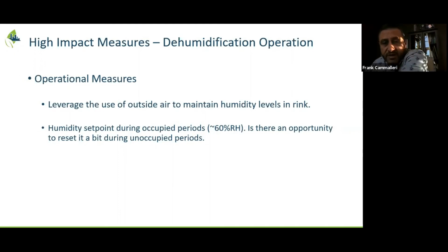Optimization opportunities exist with trying to take advantage of outside air where it makes sense. It's a trade-off with any heating that would be required, but because ice rinks typically don't have high space temperature conditions, the strategy can work quite well. We're finding that on site, humidity set points varied from one rink to the next. We've seen them as low as close to 40%, but we feel there's an opportunity to increase that setting. The higher the setting, the lower the energy required to dehumidify it.